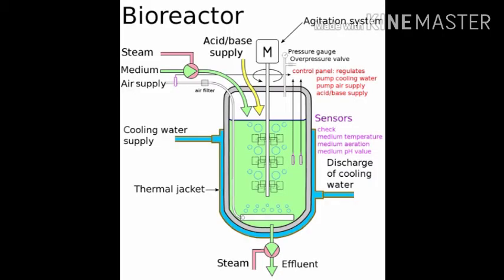Now, when we talk of the rest of the apparatus, it will have a pH balance setup. The pH probe, just like the temperature probe, is going to check the pH of the solution, and it is going to dispense as necessary. If any acid or any base is required, it will automatically dispense that. It is programmed this way because the entire system runs in a computational system and is completely automated.